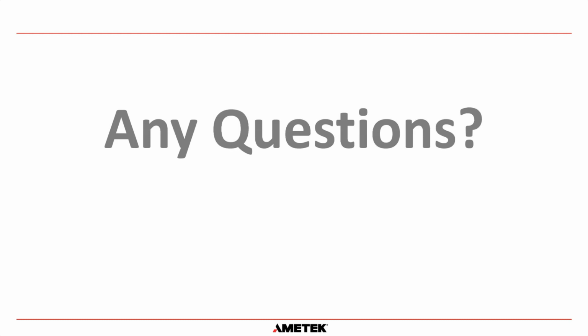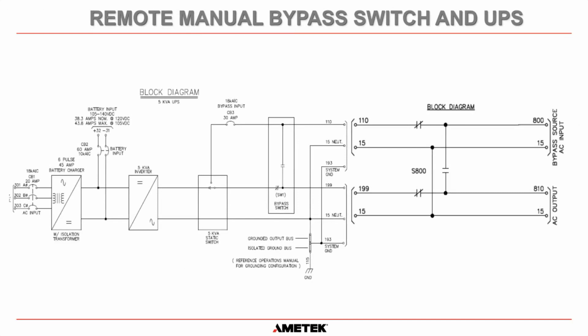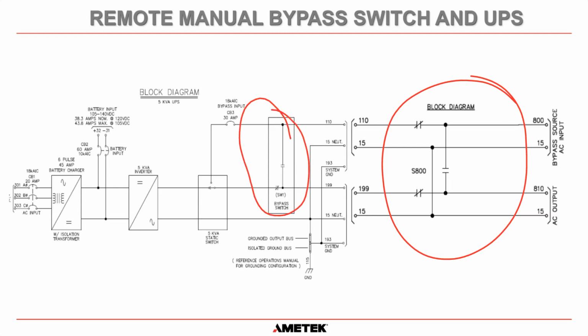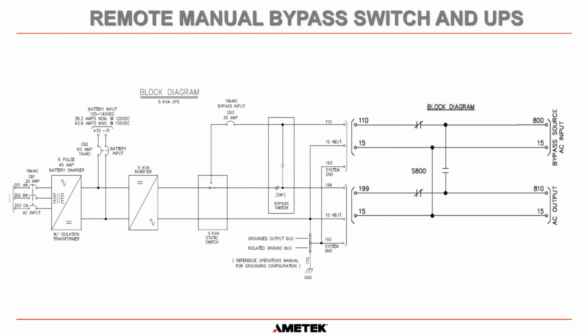And the last question I can see so far is from Cameron again. Why not both use an internal MBS and an RMBS together? That's actually a very common question. Let me go back to this screen here. In this picture we do have an RMBS and we have an MBS, so you can use them together. But the operating procedure on the front of the UPS confuses the operators at the plant, because when it says move the manual bypass switch to the bypass position, does it mean this one or this one? It gets confusing.